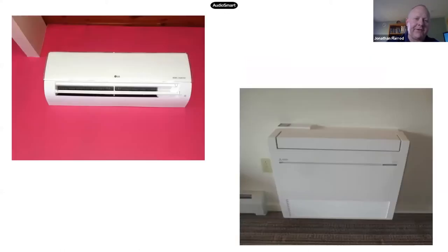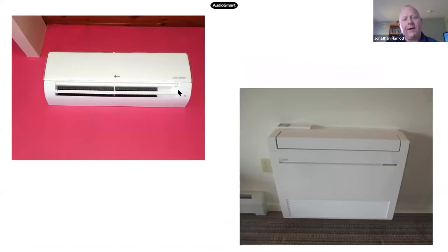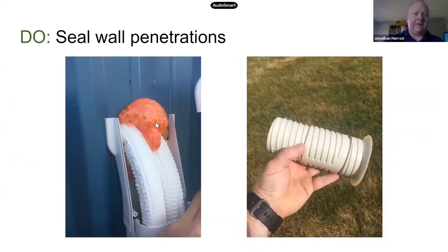And another issue that you run into is that you don't get good temperature control. The hole that allows the piping and the wires to come into the unit is about here. The sensor that senses the room temperature is about here on the unit. So if there's outdoor air leaking in and getting into the unit, it's going to throw the temperature sensing all out of whack. So we really need to do a good job. This isn't the prettiest photo on the left, but it just shows the use of expanding foam used to thoroughly seal that hole where the piping goes in.